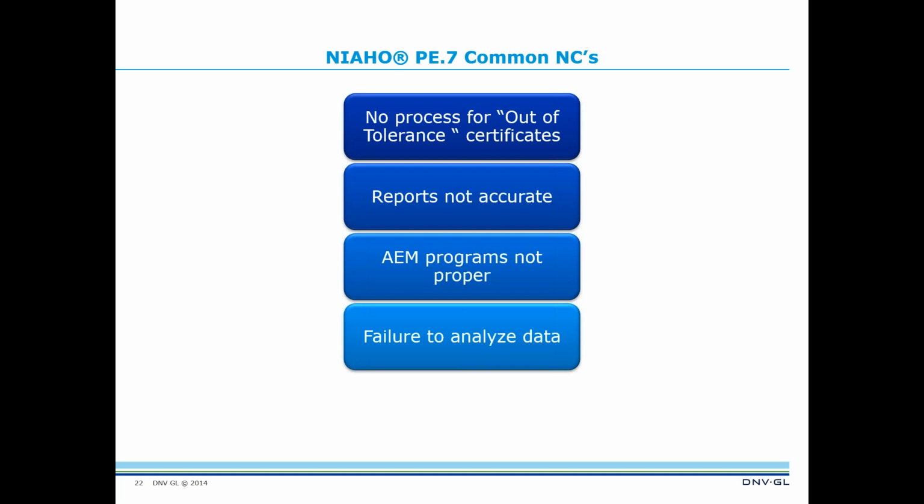What we ended up doing in our report is we had to call our programmer for our MMS or data management system and let them know not to close out a certain square until we had the test information in there. And I've never done it before I was with the DNV. We never wrote down what test equipment we used to do that device. The good thing is if a piece of test equipment came to us that was a failure, we can go back now through our database, see what equipment we checked with it, and then on critical care equipment, we have to do all the PMs over. On general equipment, you just have to do a 10% review on it. So, but as long as you do that, you're fine.